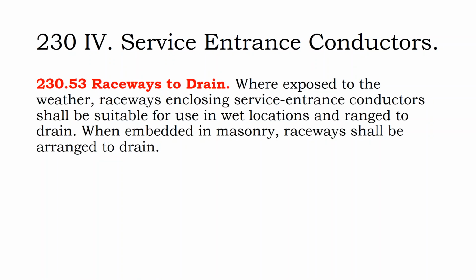So you have to arrange your raceways to drain when going into masonry. If you're doing a ground mount and you want to put a raceway through some concrete, you want to angle that raceway so that water from the ground doesn't go into your raceway, but would rather drain out of your raceway.